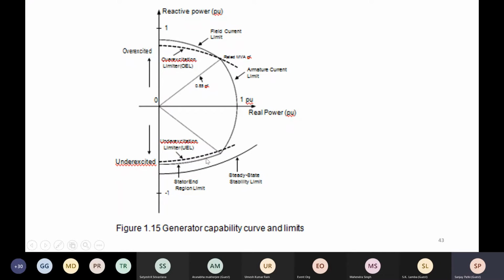But before that, there is a limitation on the generator in under excited mode, where because of the reactive power being taken from the grid, in the end region of the stator's core, the slot of the machine, there is heating due to excessive magnetic field, and the end region of the generator will become overheated. That is basically the fear because of which usually the generating units, people are hesitant to operate in this under excited region. And we'll come to this capability curve again.